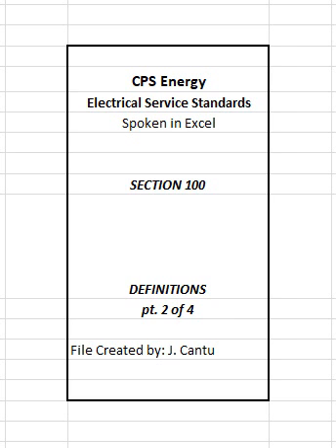Meter disconnect switch, 480 volt. A meter disconnect switch that shall be installed ahead of self-contained 480 volt kilowatt-hour meter sockets. Meter disconnect switch, distributed generation, DG. A meter disconnect switch that shall be installed ahead of a CPS Energy kilowatt-hour meter in order to isolate from DG power source.